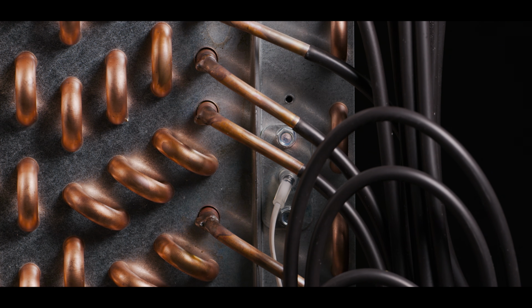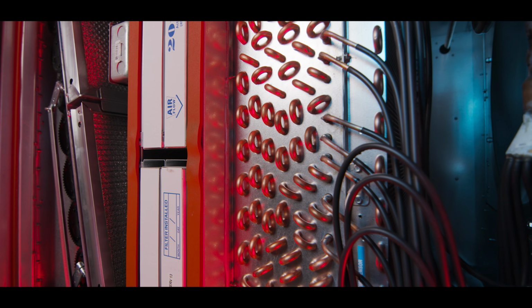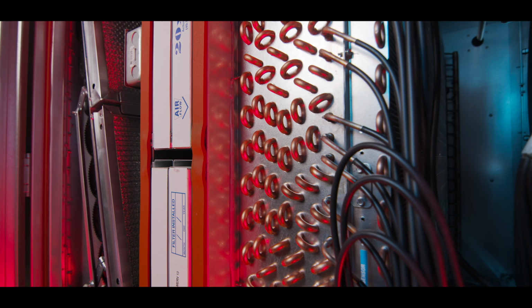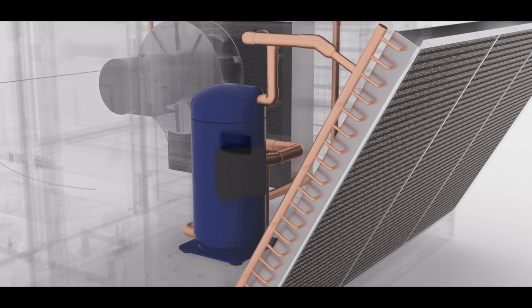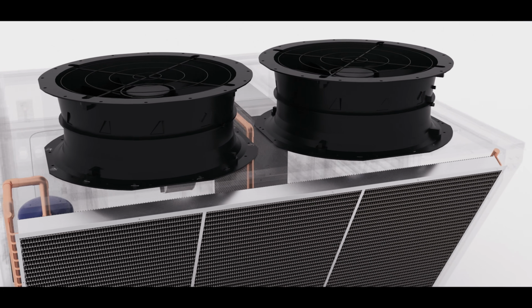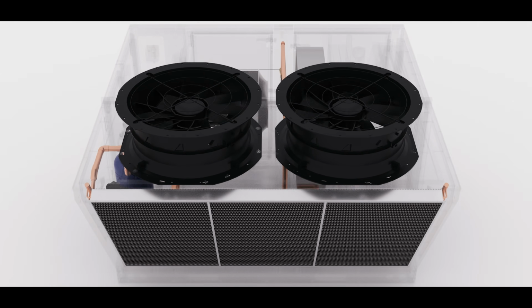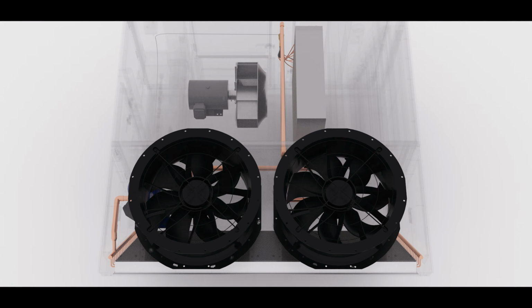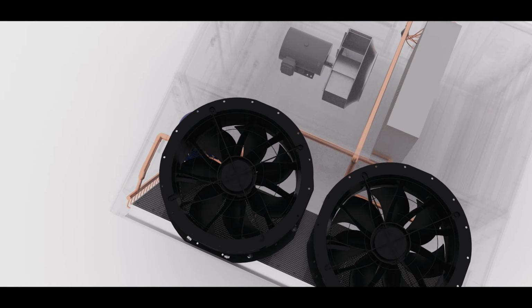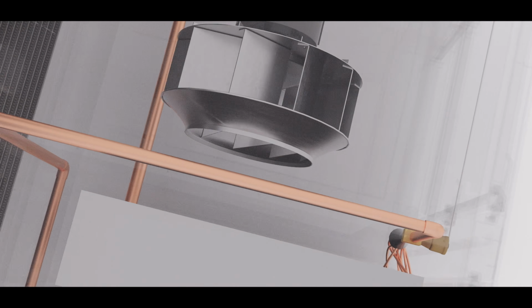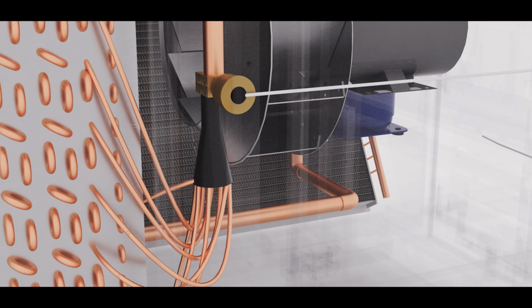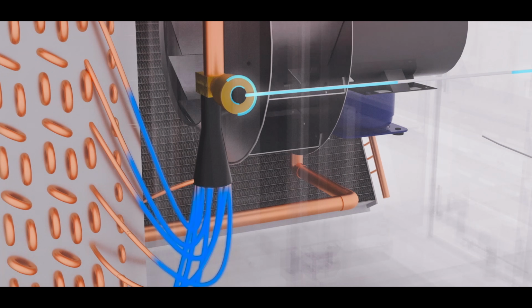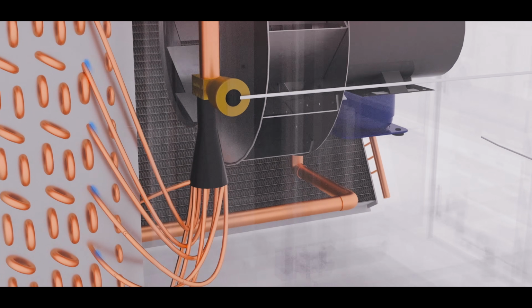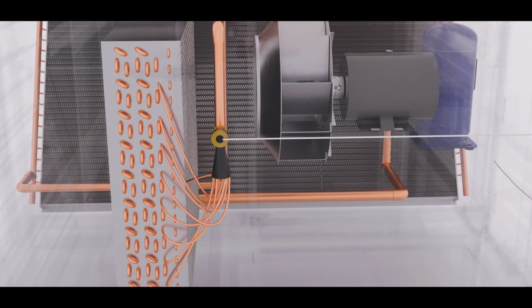On the flip side, superheat's measured at the exit of your indoor coil, right upstream of your compressor, which is also modulating. So how do you determine that you don't want your compressor fighting your EEV, even though it's a far path from the discharge of the compressor, through a lot of components, all the way to the expansion valve? They still have a little bit of a delayed effect.